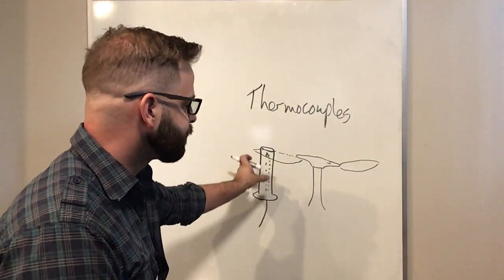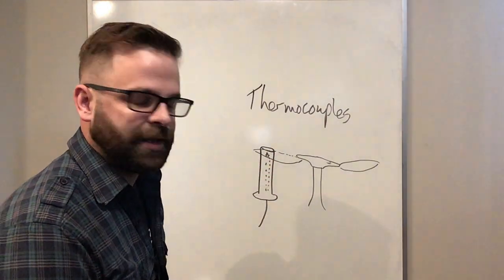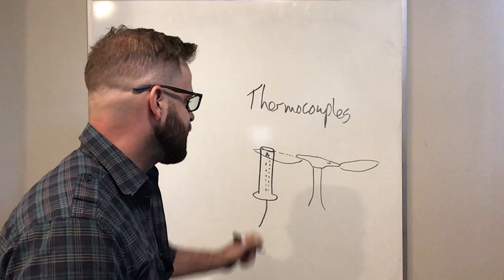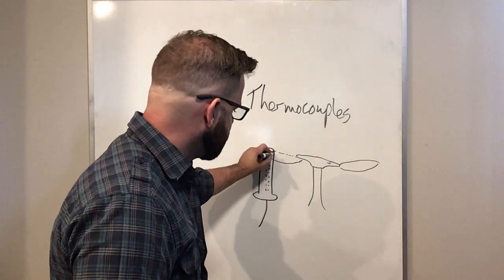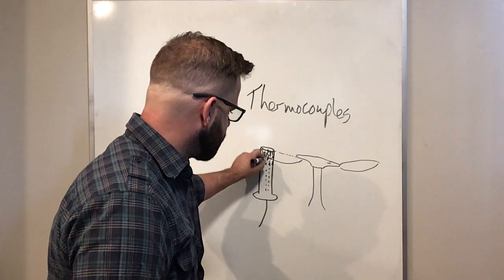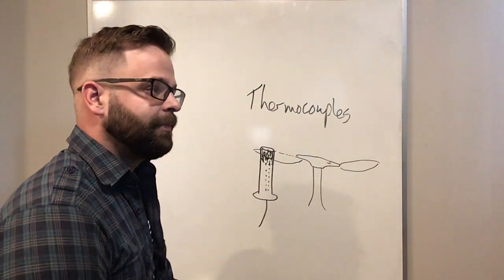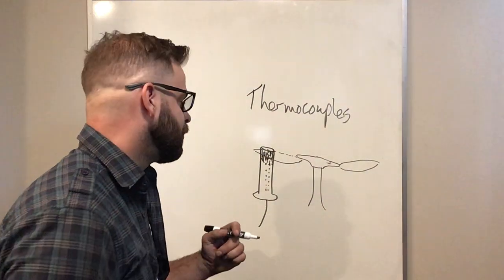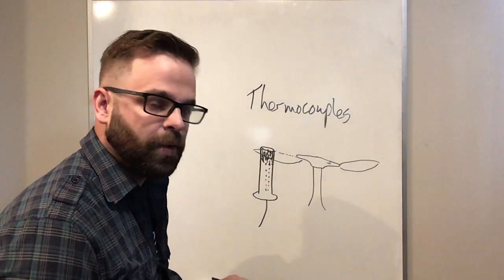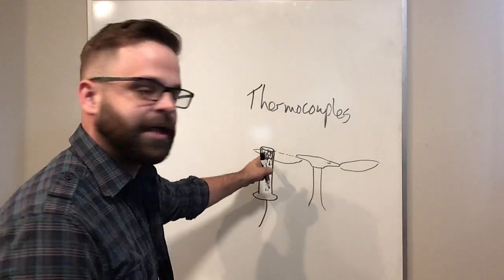However, when you put something into a flame or impinge on a flame, what can happen is I produce soot buildup on the outside of this thermocouple. And if you end up having maybe hot water that doesn't work, or you have a furnace that stops working, one of the biggest things is that I end up getting soot buildup.